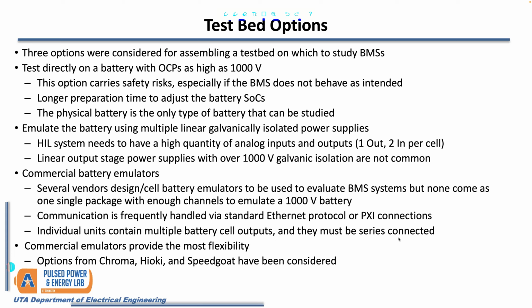One to dictate the voltage, but then one to measure the voltage and current on the output of the power supply. This results in a system that would require easily 270 times 3 analog connections. It becomes very difficult to wire, as well as to find a system with that many inputs and outputs, plus a linear galvanically isolated power supply with 1,000-volt isolation.